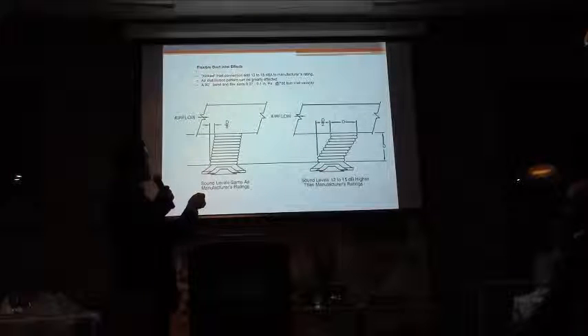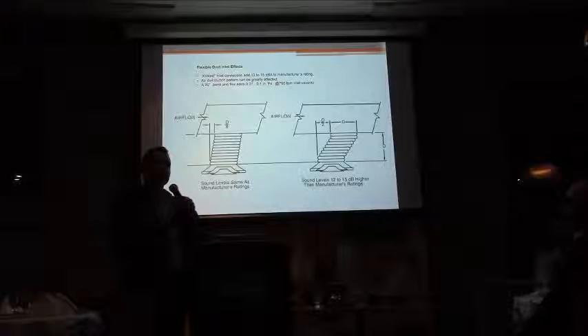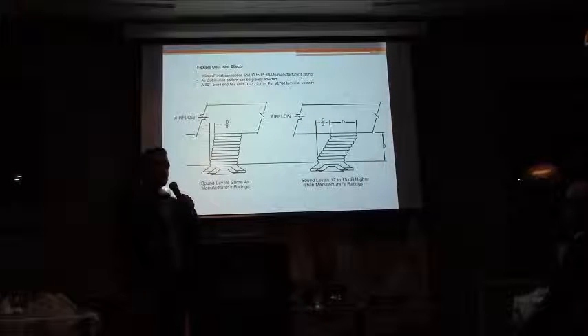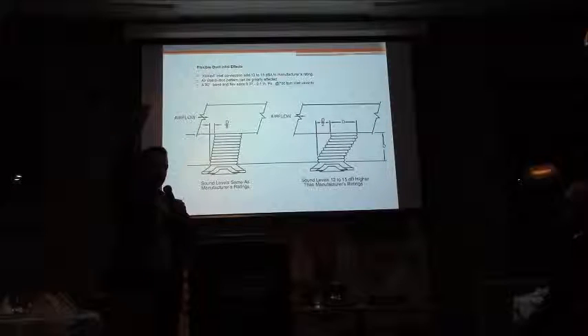So what they say is, if you have a kinked inlet connection, that adds 12 to 15 decibels to your manufacturer's rating. So if we were at 22 decibels, we just added 12 or 15 to that. So we're at 22 plus 12, that's 34 to 37 decibels. Just because you're not using a plenum, or you don't have 64 inches of straight duct before your diffuser.